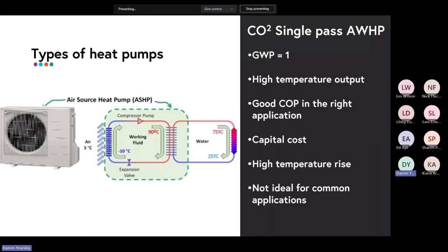It has very, very high temperature output. So you can reliably get up to 80 degrees on the flow, which obviously opens up the domestic hot water production where you want to keep your tank at 65 degrees for sterilizing. So that's very possible with a CO2 heat pump. In the right application, a CO2 heat pump is very, very good. I'll just explain about some of the limitations and what single pass means in a minute. In terms of capital cost, they're reasonably expensive, but not ridiculously so. So on a cost per kilowatt basis, they're a bit more expensive than an R32 or even an R290 appliance, but they still create some value.